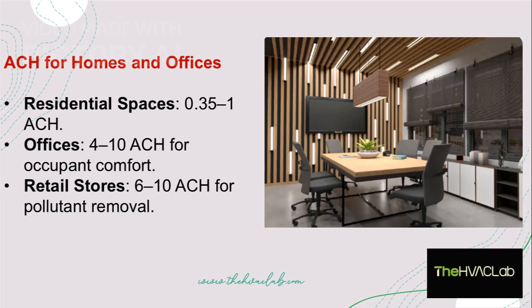For residential spaces, the recommended ACH is between 0.35 and 1. Offices and retail stores require higher ACH values, ranging from 4 to 10, to ensure occupant comfort and pollutant removal.